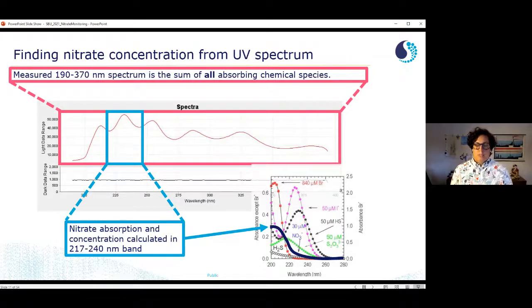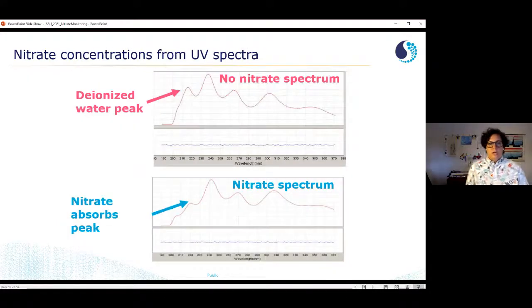That's the nitrate absorbance peak. And you'll see that peaks between that band. That's really the key piece of the UV spectrum that we're looking at to understand how much nitrate is in the water. So we can look at the spectrum. We can look at it actually two different ways. So what the nitrate concentrations look like from the UV spectra.